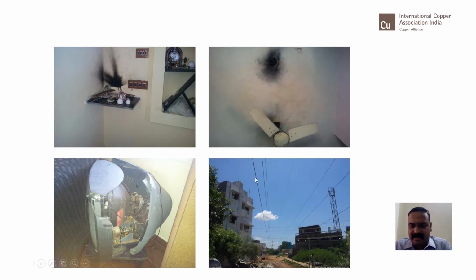There was a high tension wire going just close to the building, and below it there was a crossing of a low tension line entering into the building. The distance between both the cables was not sufficient. Probably the lightning would have struck the building and the side flash would have struck this cable, and the electromagnetic interference would have entered through the low voltage line. And only when the surge enters this network, obviously all electrical equipment connected on that particular network can have a failure.